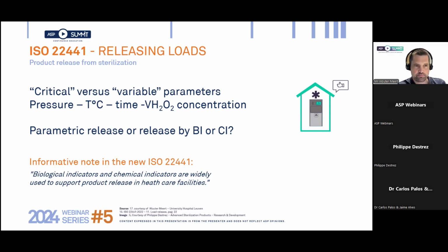And like Philippe told, it's pressure, temperature, time, and of course the hydrogen peroxide concentration. Does this mean that in every release of a load, you need to check all those parameters? Or are some of them okay? And do you need to check all the parameters of all the process steps? Of course, it is not the case. So, am I going to do a parametric release, or am I really using BIs or CIs? That's something that's suggested in most countries, and maybe in some countries regulations oblige you to do some BI or CI. But I think it's really important that within your quality system, with your quality team and in daily practice, you find the best way of releasing.